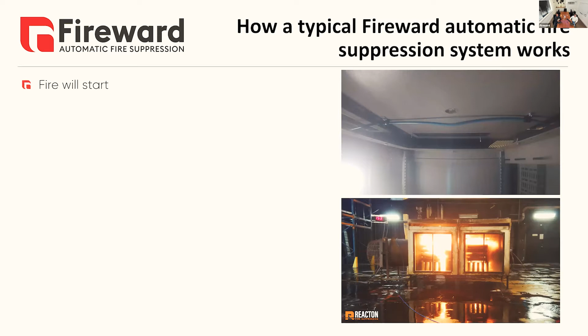So we'll just go through really the sequence of how the system works from start to end. And really, with a Fireward automatic suppression system, the fire will start. This could be caused by a short circuit, an overloaded cable, diesel spray going onto a hot surface. Whatever the situation is, that will provide radiant heat, and that bursts the detection tube and activates the fire suppression system. And the videos we've got here, the top one will show you what that looks like with a direct technology for your control cabinets and so on. And then the bottom one is an actual very high energy fire from the Research Institute of Sweden, where we do our testing. But in summary, the tube will burst and initiate discharge at the source of the fire. We're actually detecting and putting it out exactly where it starts.